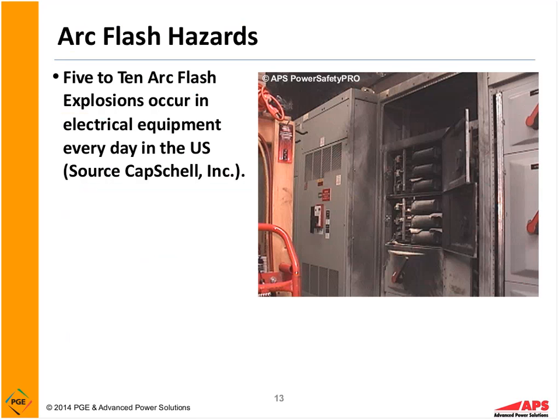This picture, by the way, in the upper right-hand corner is a picture from a friend of mine in Ohio who has a maintenance business. He just went in and opened up a 600-amp fusible disconnect. And he opened it up and it arced. And the door was closed when it arced. But there was an electrical explosion. When we talk about arc flash, that's an electrical explosion. The arc blew around the edges of the door, burned a hole through the door, and blew the door open. Now, he did receive some burns, okay?